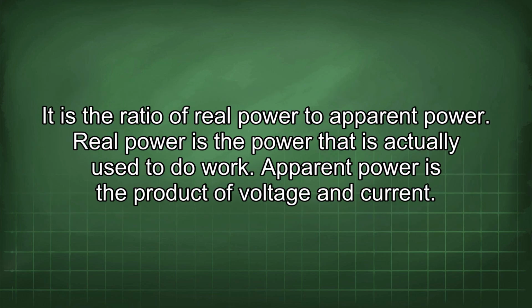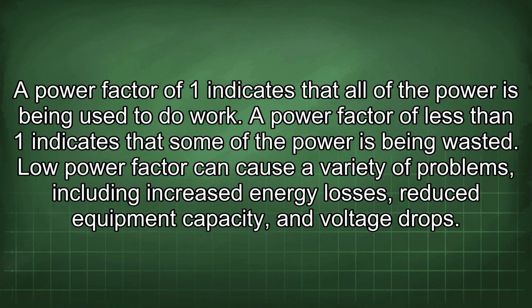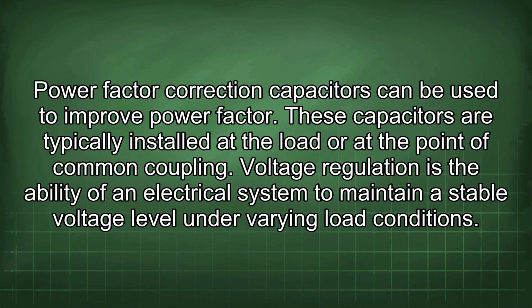Power factor is a measure of how effectively electrical power is being used. It is the ratio of real power to apparent power. Real power is the power that is actually used to do work. Apparent power is the product of voltage and current. A power factor of 1 indicates that all of the power is being used to do work. A power factor of less than 1 indicates that some of the power is being wasted. Low power factor can cause a variety of problems, including increased energy losses, reduced equipment capacity, and voltage drops. Power factor correction capacitors can be used to improve power factor. These capacitors are typically installed at the load or at the point of common coupling.